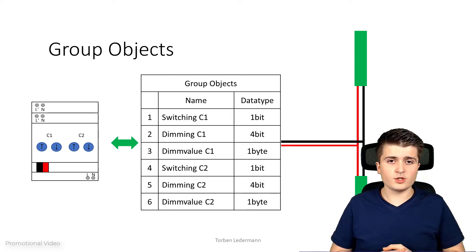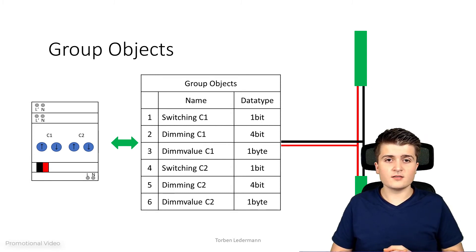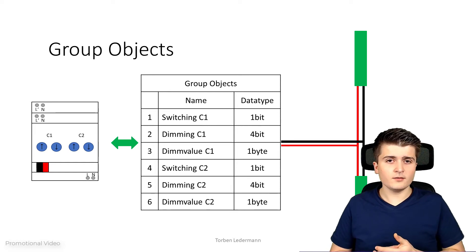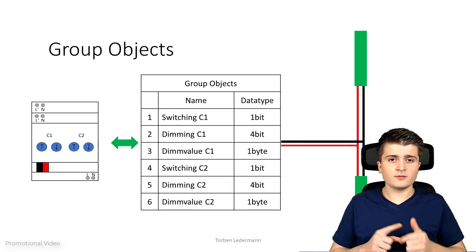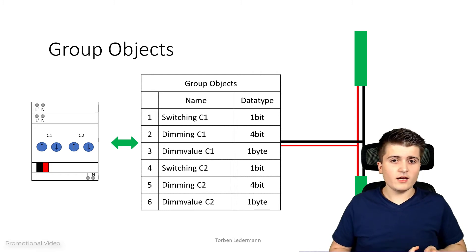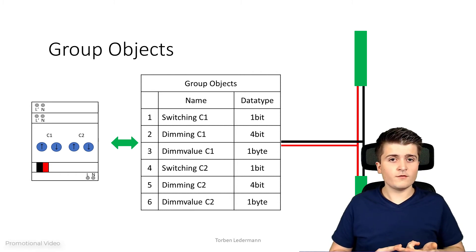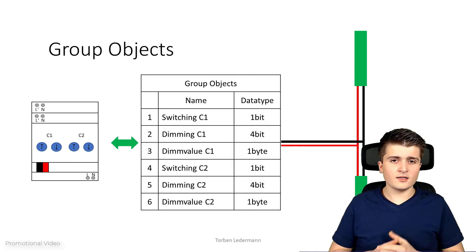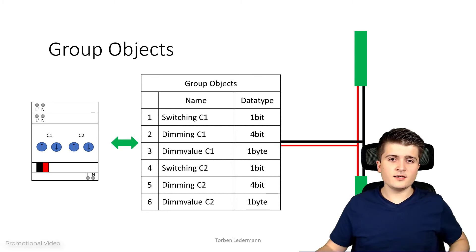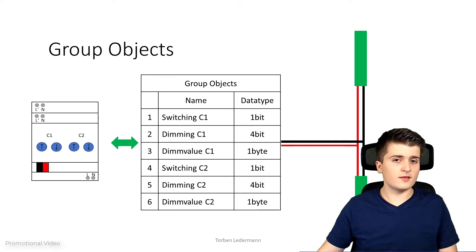In the case of switching, the data type is one bit. In the case of the dimming value we have a size of one byte. And for dimming control — with values like dimming up, dimming down, and dimming stop — we have a size of 4 bits. Now that we saw the theoretical approach for group objects, let's take a look at ETS6 to see them in practice.